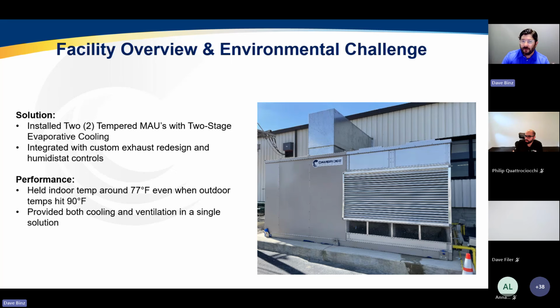But what we deployed here was actually utilizing 2-stage temperature relief with 2-stage evaporative. So evaporative technology can be extremely energy efficient, and in many high internal heat gain applications, by delivering neutral air, when I say neutral, maybe even space temperature neutral, like 75-degree air in a 110-degree environment, can actually provide enough temperature relief without using a lot of energy. 2-stage evaporative cooling can actually get your discharged air temperature below the ambient wet bulb while utilizing a fraction of the energy that you would with mechanical cooling.